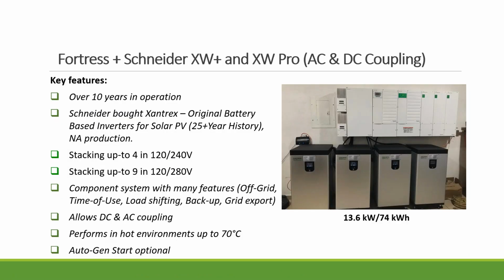Now I'm going to use a Schneider inverter as an example because this is equipment that you have. It's very flexible in terms of when you design them. Depending on your PV array, you can determine how many charge controllers you want, and depending on your load, how big your critical load panel is. You can select inverter sizes, and then depending on how many days of autonomy you want to achieve, you can select the battery banks.